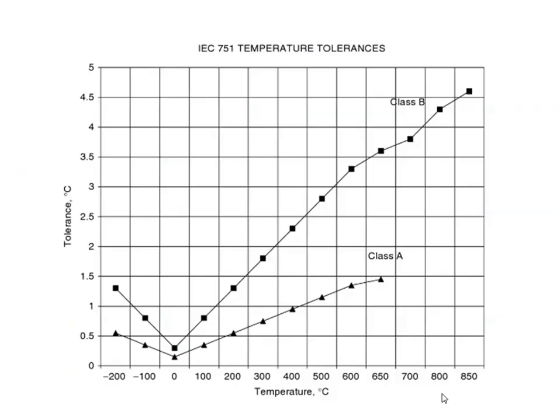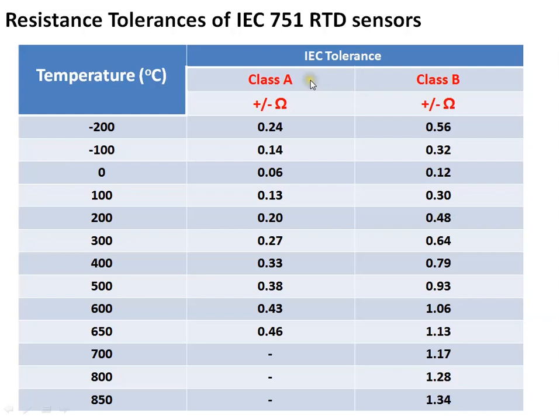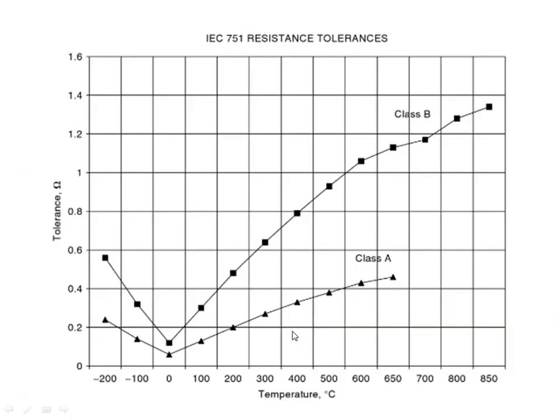Here you can see a table for Class A and Class B showing temperature versus temperature tolerance. With increase of temperature the error also increases. This graph shows temperature versus tolerance for Class A and Class B — for applications requiring good accuracy you can go for Class A, but the temperature range is limited. For higher ranges you can go for Class B, but accuracy is lower. This table and graph show the resistance tolerances versus temperature for Class A and Class B — Class B resistance tolerance increases with increase of temperature.